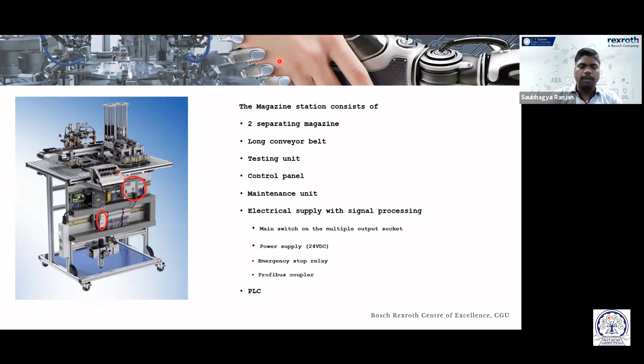So see, if you take a simple example, just let it be clear. So this is your PLC, and suppose you have 20 input outputs here and here and here. For 20 input outputs you need power supply for each input and output, and even if you take a common power supply, there will be 20 cables running from here, from the PLC to the input output module, right? Similarly from here and similarly from here. So instead of them, let a single signal come from here to here, and here we'll add a processor which will process the data and simply give these signal modules on or off. So this is what we do using the remote IO. Clear? Yes. Yes. Okay.